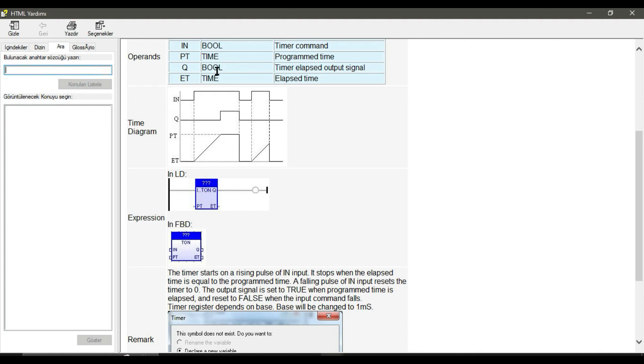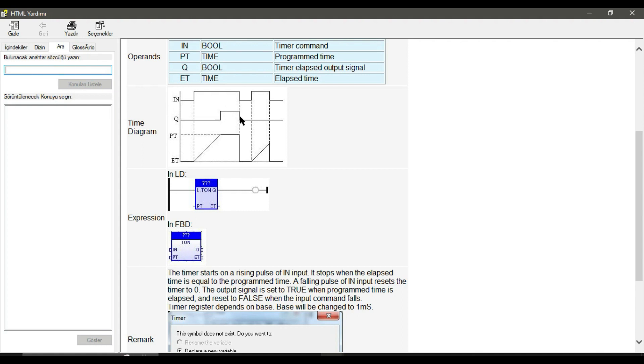Let's take a quick look at the timer diagram and how it works. Remember that it is an on delay timer — it turns the output on after a delay. This is the input, output, preset time (PT), and elapsed time (ET). As soon as the input turns on, the elapsed time counts the time until it reaches the PT or preset time, which is the delay for the timer. After this delay time, the output turns on.